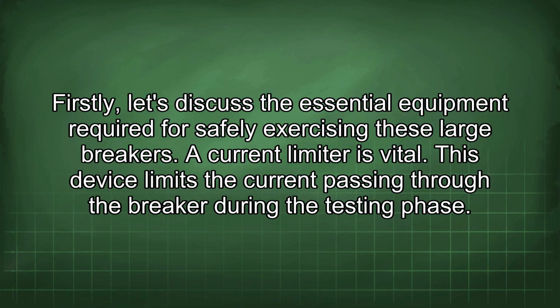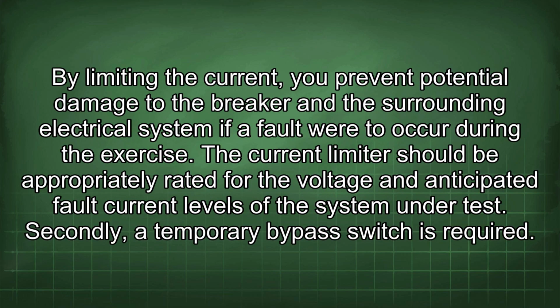Firstly, let's discuss the essential equipment required for safely exercising these large breakers. A current limiter is vital. This device limits the current passing through the breaker during the testing phase. By limiting the current, you prevent potential damage to the breaker and the surrounding electrical system if a fault were to occur during the exercise. The current limiter should be appropriately rated for the voltage and anticipated fault current levels of the system under test.